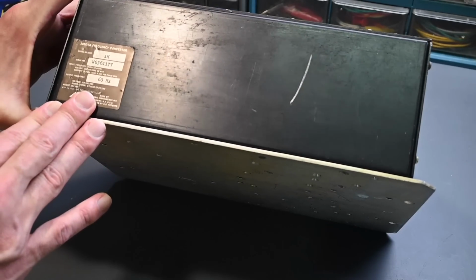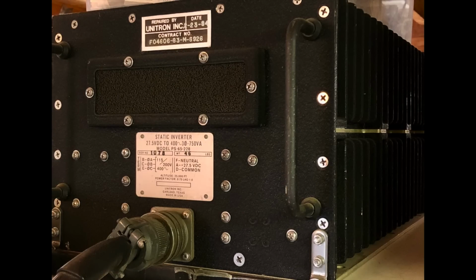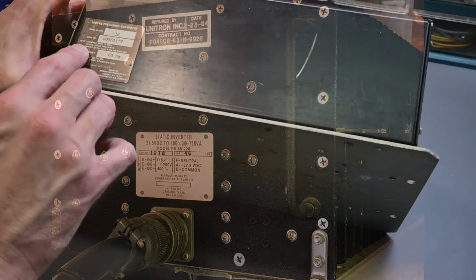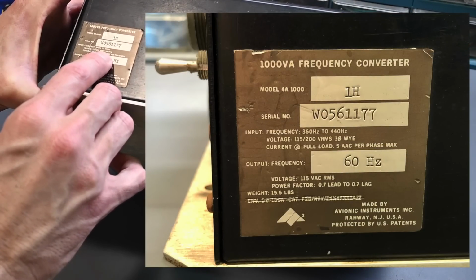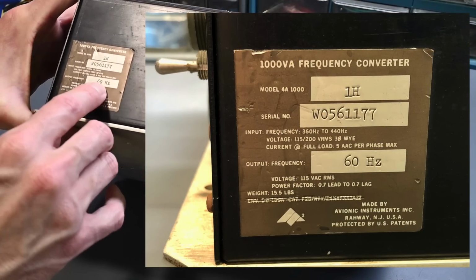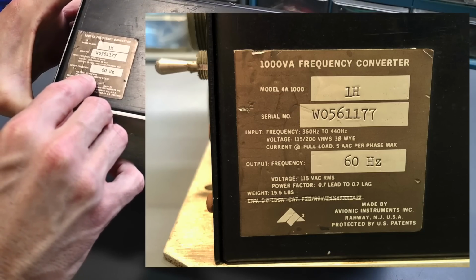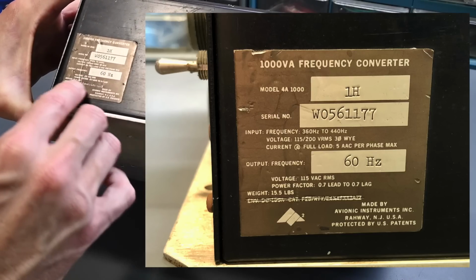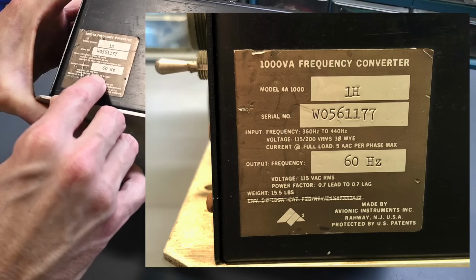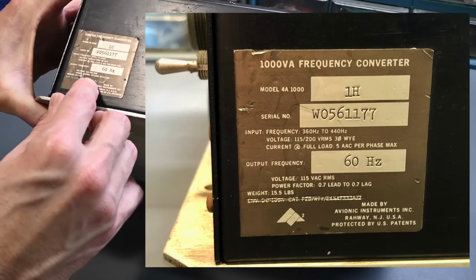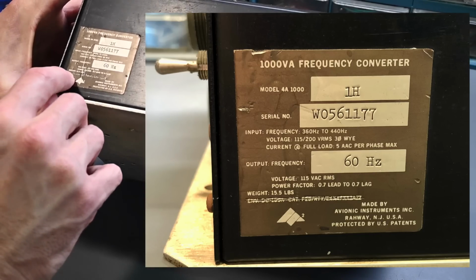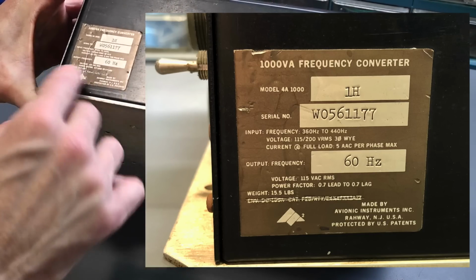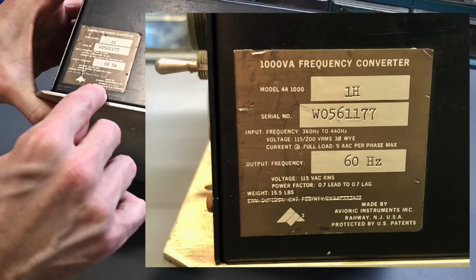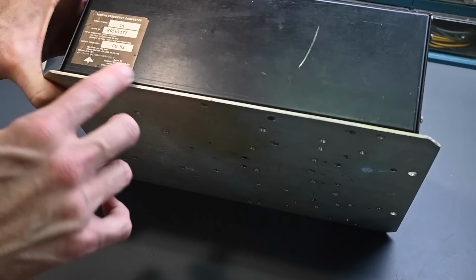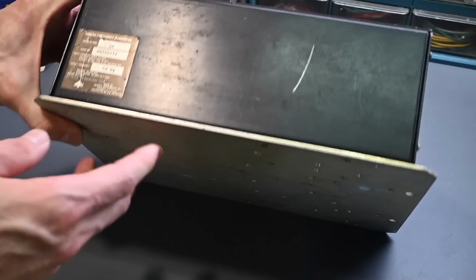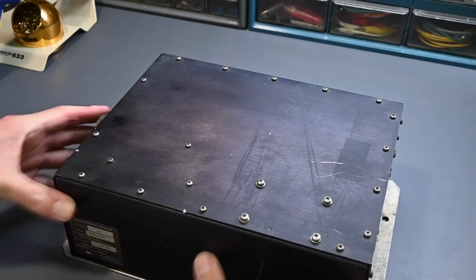I won't go into details on that inverter, other than it is a Unitron PS65228. The current here listed at full load is 5 amps AC per phase, and the output frequency is 60 hertz, voltage 115 volts RMS - single phase on the output, not three phase. It says power factor 0.7 lead to 0.7 lag, or 70% lead, 70% lag. Weight, 15.5 pounds. There's some other long number, not sure if it's a catalog number, looks like it was crossed out, but that's not really important. It was made by Avionic Instruments Incorporated, and they're still in business. I don't know the year of production or anything else about this unit - those are really the only markings on this device.